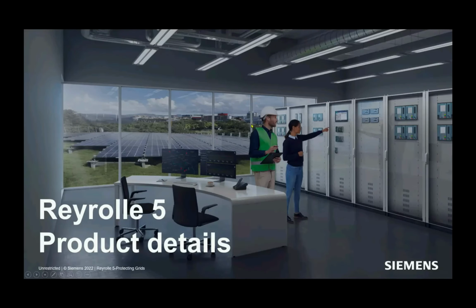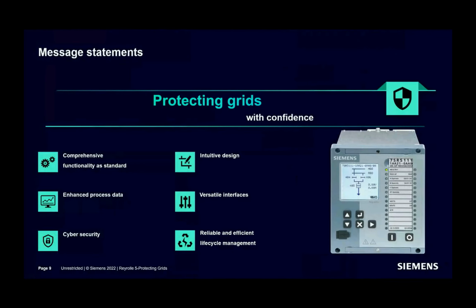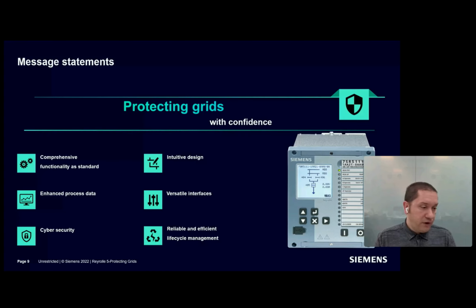Now, let's go a little bit further with the details. As a standard, all listed protection functionalities and major Ethernet communication protocols are included as standard. All Reyrolle protection relays, including Reyrolle 5 and all other Reyrolle portfolio actually, are enabled to serve all the protection functions that the chosen hardware is capable of. So once you choose the hardware, you will have all the functions listed dedicated to that hardware configuration at all.